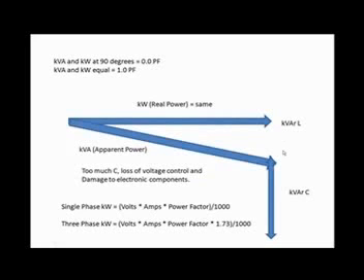What happens is you end up with way too much capacitance in the circuit. Your power factor changes to KVAR capacitive. And what ends up happening with KVAR capacitive is that you lose voltage control and you begin damaging the electronics in your home — meaning you'll start to see TVs, stereos, computers, all that stuff begin to fail.